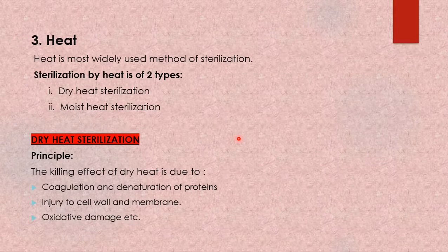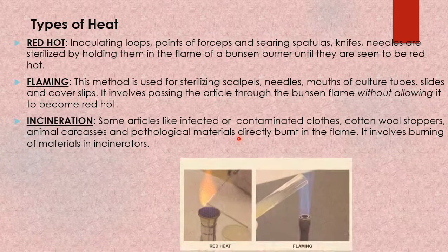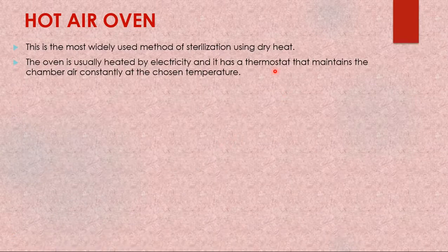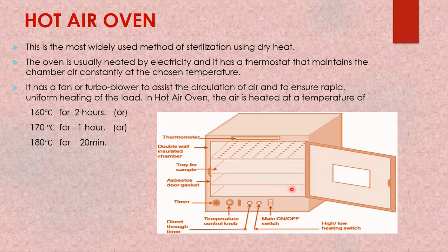The next and very important type is the hot air oven. Dry heat sterilization is carried out in an electrical chamber called a hot air oven. It consists of a double-wall chamber fitted with electrical heating elements. A fan is featured inside to evenly circulate the hot air throughout the chamber.